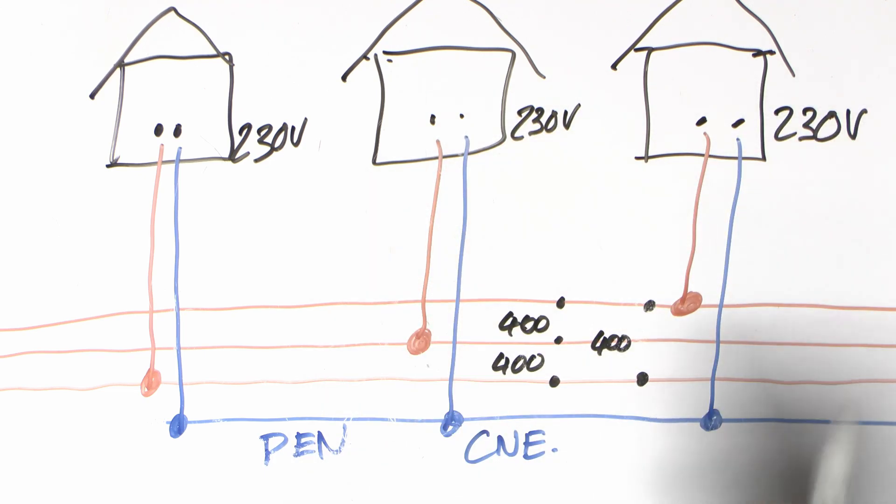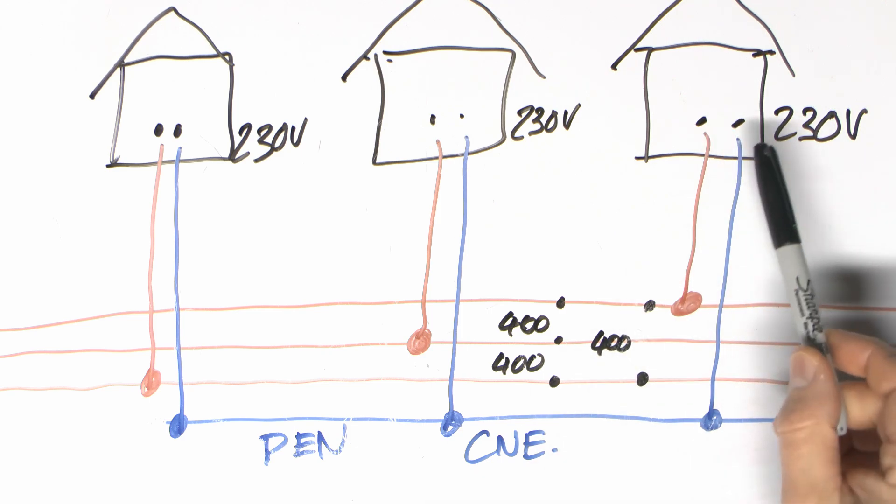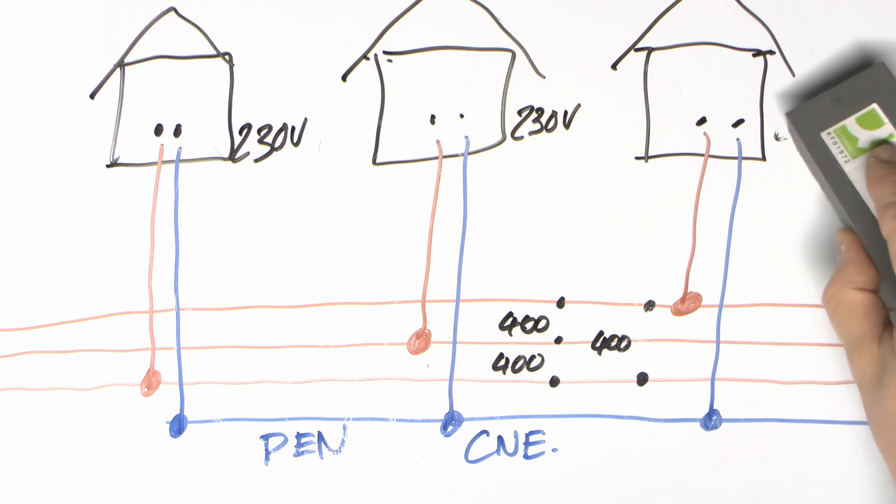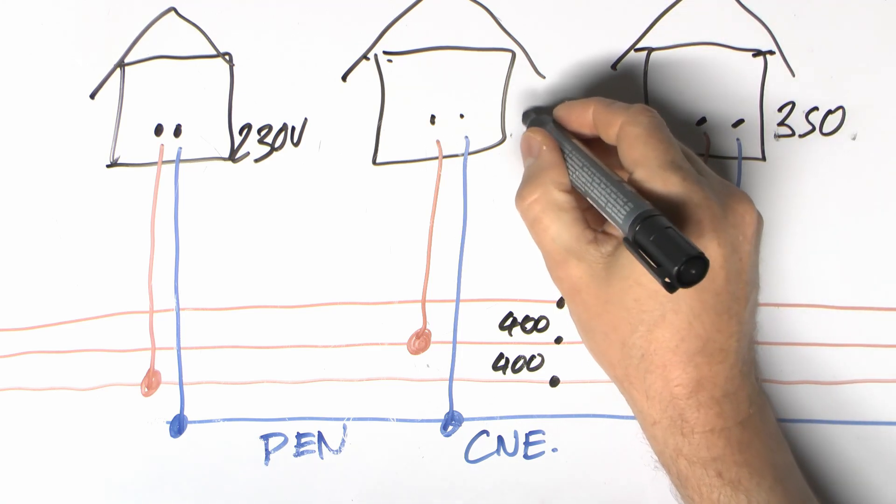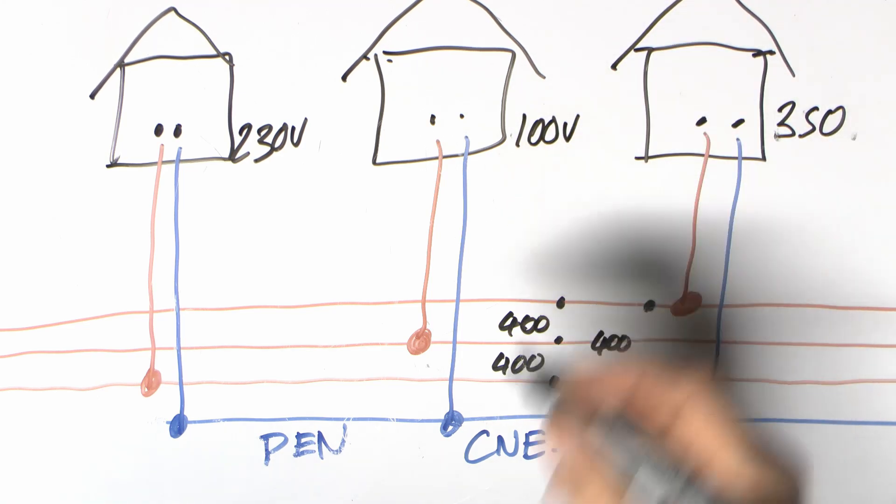what's going to happen is that this point here is going to be shifted to its maximum extent and you're going to end up with some of these properties getting almost no voltage. And, unfortunately, some of them might get anything up to the full 400 volts between these two. So instead of 230 there, you might see something like 350. And, again, this will depend on the loads you've got. These people here might only get, say, 100. And you can imagine this repeating down the entire street. Who knows what could happen?